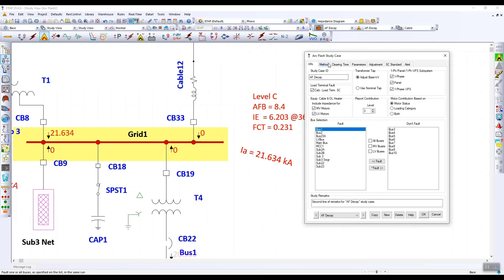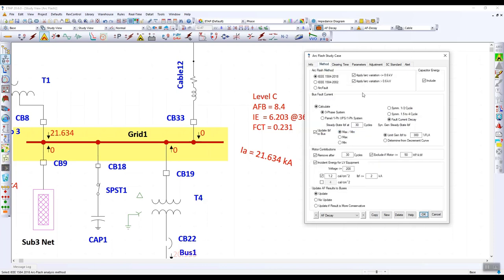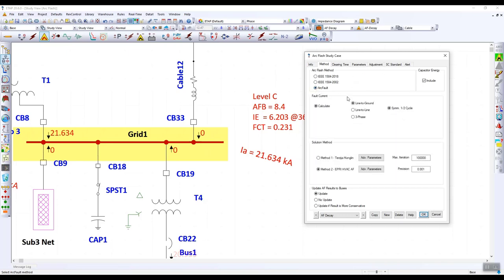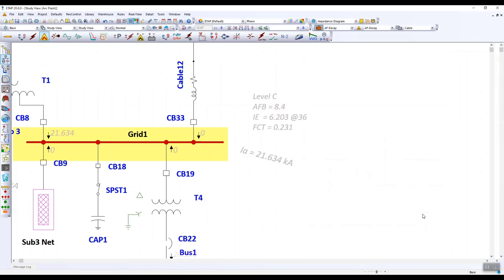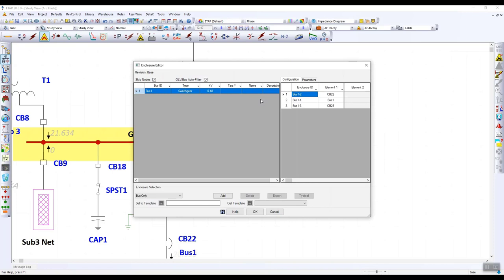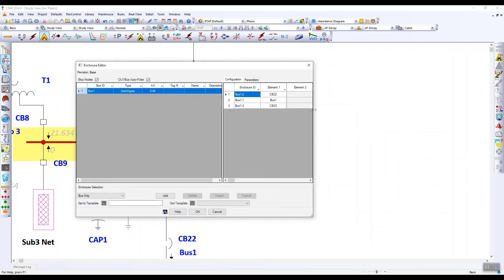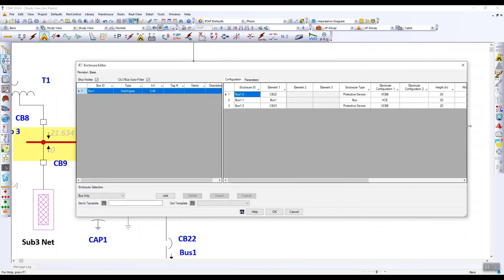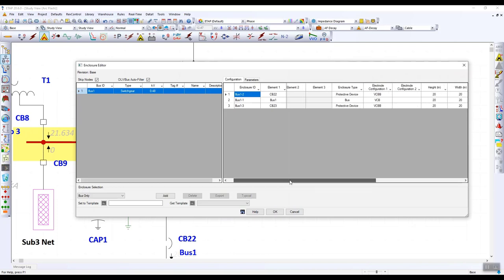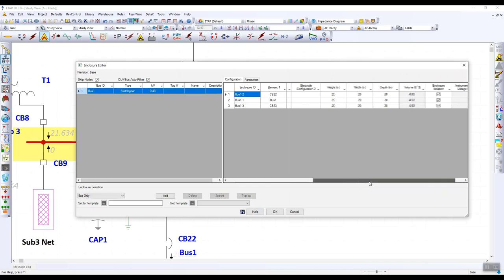In the Methods tab, we can choose which standard we'd like to apply, like IEEE 1584-2018. We can also choose the arc fault method if we'll be evaluating a system over 15 kV. Now, since we are using the IEEE 1584-2018 standard, we can open up the enclosure editor and specify the dimensions and also select which bus or protective device belongs to this enclosure. On the right, we see which devices are in this enclosure, the enclosure type, the electrode configuration, and the dimensions.